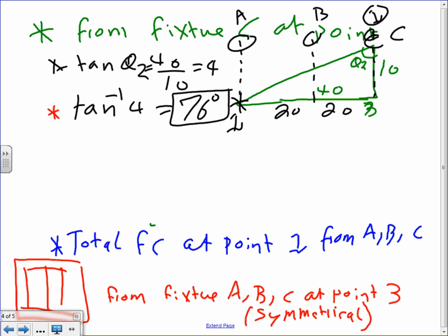Okay, then you're going to start plugging it in. See how easy that is? Then the foot-candle equals 0.88, the guard factor. Now we need to find the candela power at 76. Do I have a 76? What do I have? I have 75. The closest is 75, so take 75. That will get you 194.